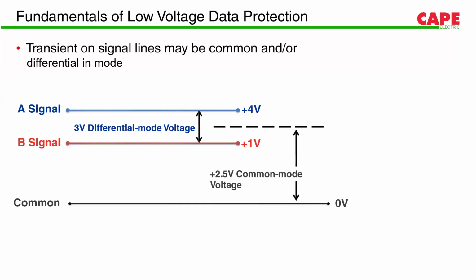Generally signal communication can be of two types, differential mode or common mode communication. Suppose there are two wires, wire A and wire B, carrying a signal. If the communication is happening between both the wires, it is called differential mode communication. If the communication is happening between signal wire A and the common wire, it is called common mode communication. An SPD should provide protection against both modes.